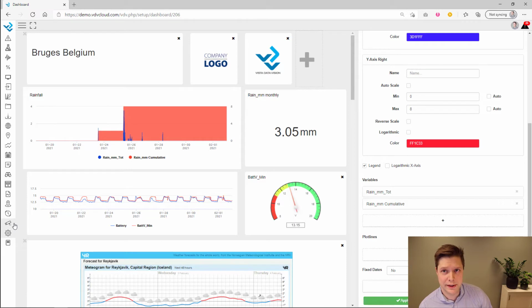So there is a time shift in the data. To be able to have the data update alarm precise, so if the data is not updated for 2 hours, 4 hours, 6 hours or so, you need to tell the system what time zone your data is in. So it can then calculate how old the data is and then send a data update alarm if the data gets too old.